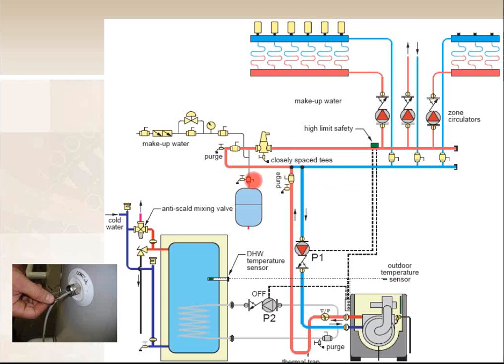There's other ways to do it other than the closely spaced T's. You can use those Taco twin T's. You could use like a Caleffi hydraulic separator. You can use a boiler buddy. There's different ways to do it, but the closely spaced T is the least expensive way to get your dedicated primary and secondary loop. And in this example, we have 3 secondaries. The other thing that you see in this drawing is that we have an indirect domestic tank, kind of like I talked about for the rebates for the utilities.